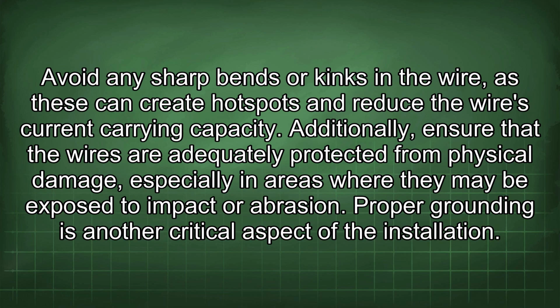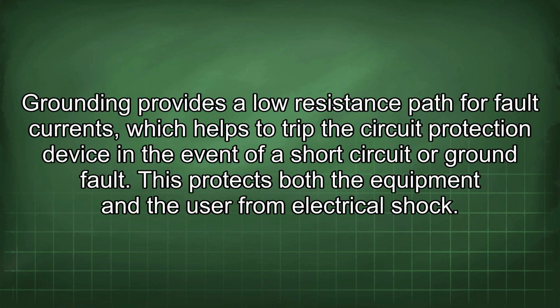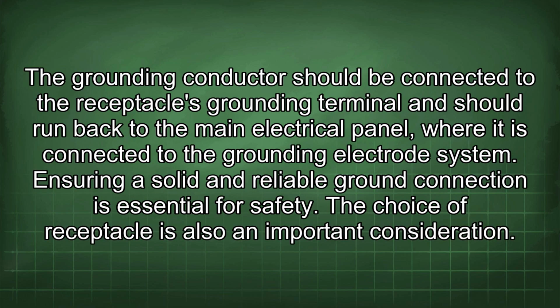Proper grounding is another critical aspect of the installation. Grounding provides a low resistance path for fault currents, which helps to trip the circuit protection device in the event of a short circuit or ground fault. This protects both the equipment and the user from electrical shock. The grounding conductor should be connected to the receptacle's grounding terminal and should run back to the main electrical panel, where it is connected to the grounding electrode system. Ensuring a solid and reliable ground connection is essential for safety.